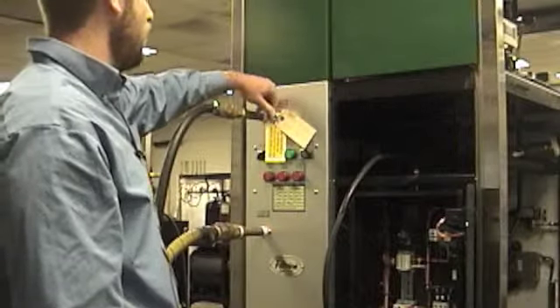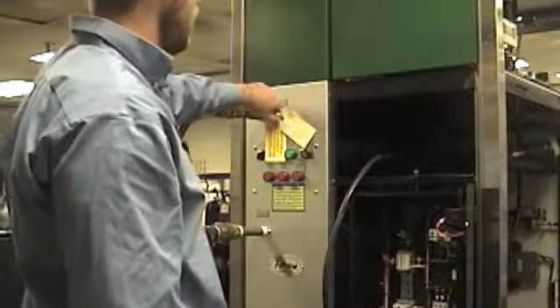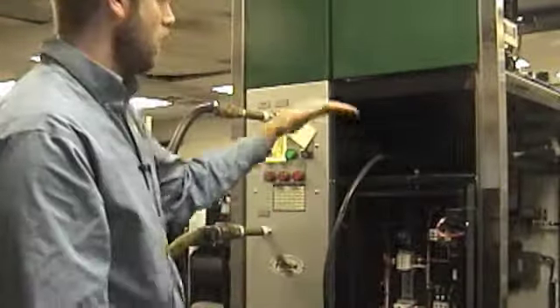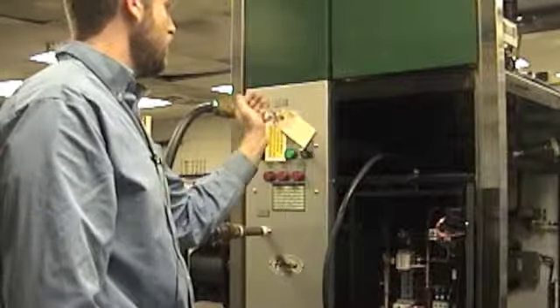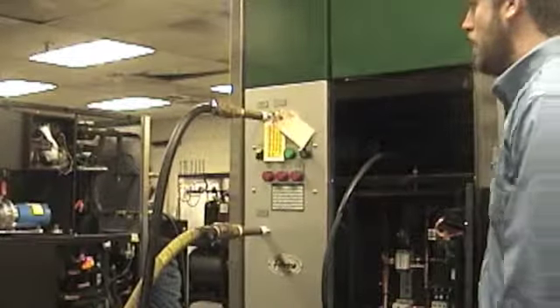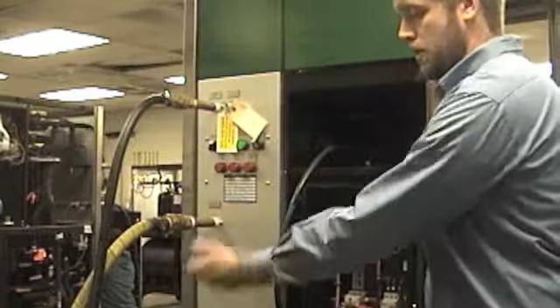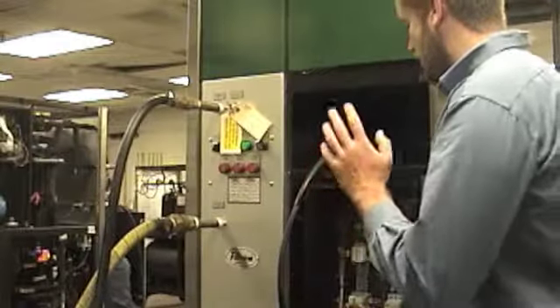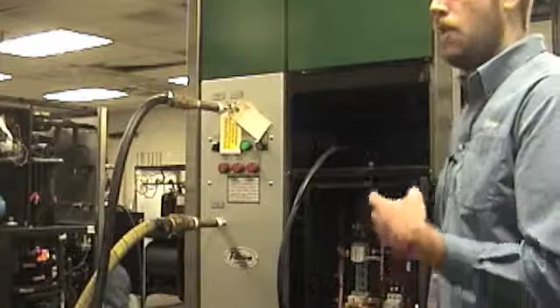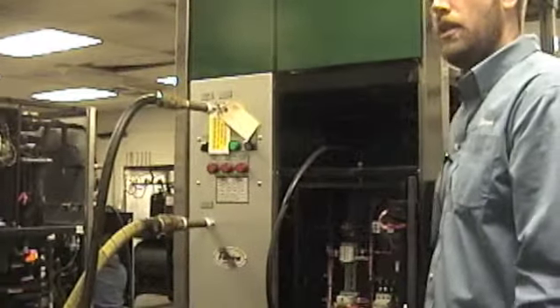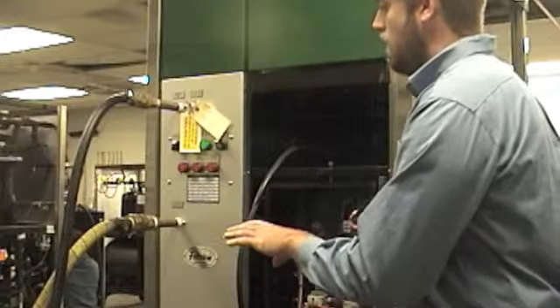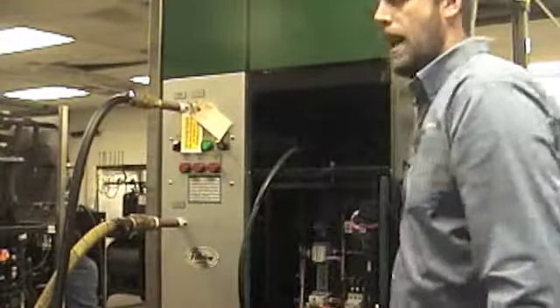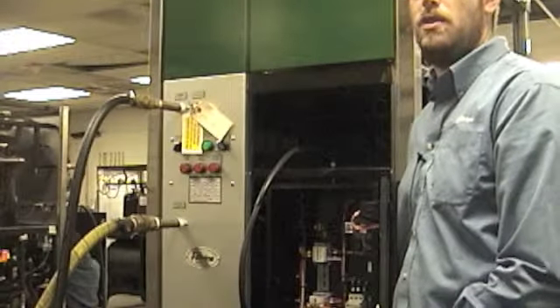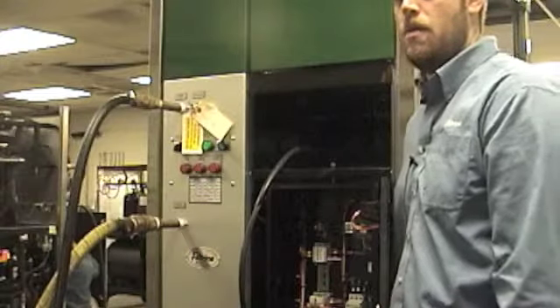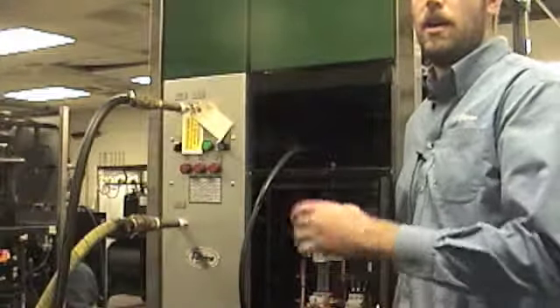So to fill the unit, you have your air release right here and your water in. So you turn it on, bleed the air, and allow the tank to fill from the bottom up. Once you get a steady stream out of the air release, you know that most of the air is out of the system. You can either put a large hose over that or just let it spill into a bucket when you're filling. You want to make sure that you get as much air out of the system as possible before starting it up, so you don't have air in the lines and around the pump. On these, you also are going to have to bleed air out of the actual loop serving the fountains. Sometimes the best way to do that is through the bubblers themselves once you get the pump going, and you can bleed out the air that way.